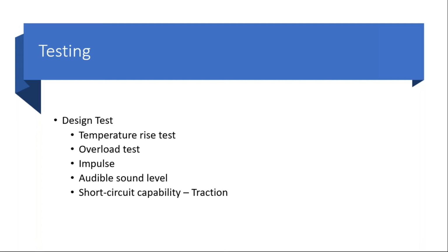So, impulse and audible sound level. They're standard, but most of the time the LVs are rated for 500, 600 volts, which are not commonly subjected to impulse test. It's generally designed for 30 BIL, and 30 BIL, if it has a very high capacitance, the wave shape is not right, and 30 BIL does not make sense to do an impulse test. So impulse test most commonly is on the HV side.